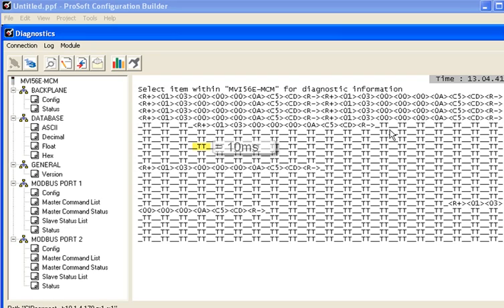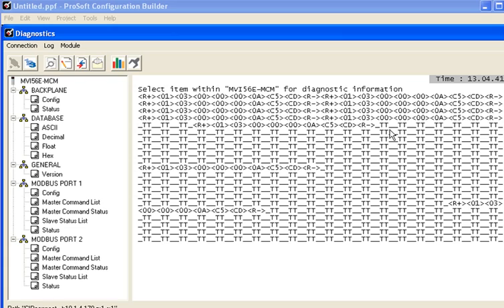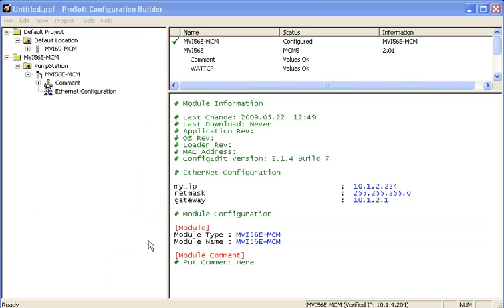Okay, notice that each underscore capital TT underscore. So that's four characters: an underscore, a capital T, another capital T, and another underscore. So each underscore TT underscore, that is one 10 millisecond tick. Now right now I don't have any slave devices connected to my Modbus network, so in this data analyzer you don't see any response data coming back. All you see is the R plus, which signifies that the module is generating traffic for that port, so it's taking the line high. And then you see the 8 bytes for the Modbus read function. And then you see the R minus, which signifies the module is releasing the line.